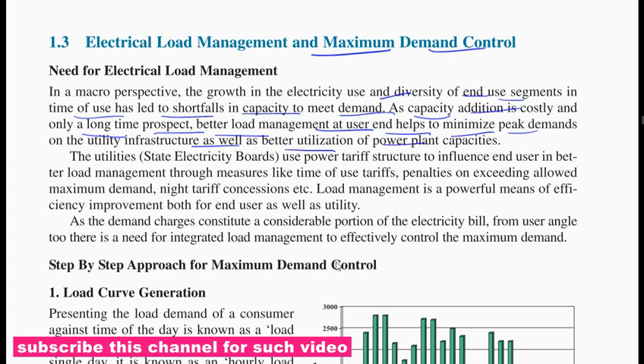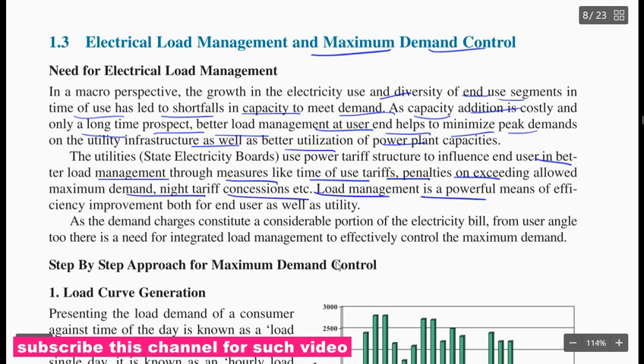The utility, the state electricity board, uses the power tariff structure to influence the end user towards better load management through measures like time of use tariff, penalties on exceeding allowed maximum demand, and night tariff concession. Load management is a powerful means of improving efficiency for both the end user and the utility. As the demand charge constitutes a considerable portion of the electricity bill, from the user angle too there is a need for integrated load management to effectively control the maximum demand.